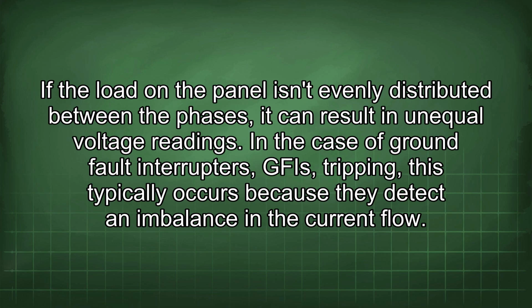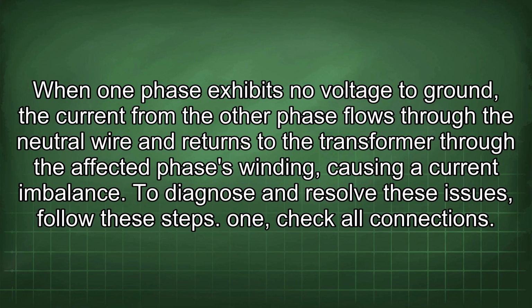In the case of ground fault interrupters, GFIs tripping, this typically occurs because they detect an imbalance in the current flow. When one phase exhibits no voltage to ground, the current from the other phase flows through the neutral wire and returns to the transformer through the affected phase's winding, causing a current imbalance.